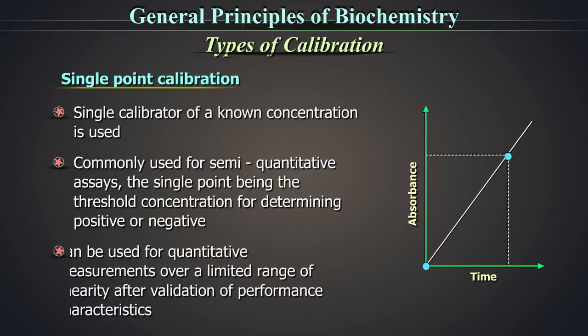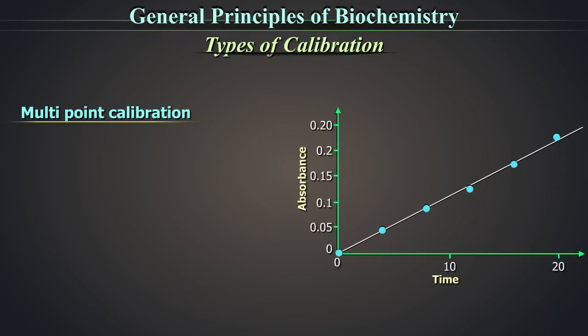This can be used for quantitative measurements over a limited range of linearity after validation of performance characteristics. Multi-point calibration: Two or more different calibrator concentrations are used. The calibrator should preferably span the entire range of analytical values for the given analyte.